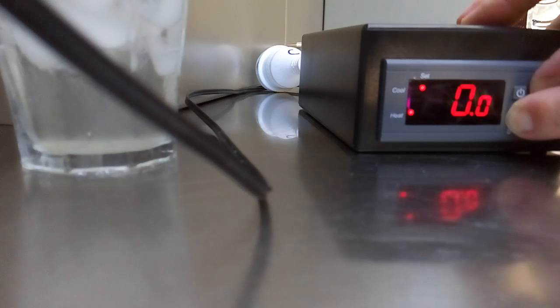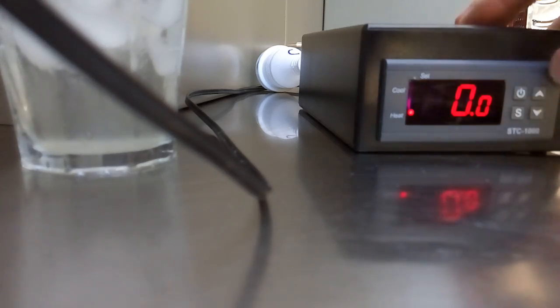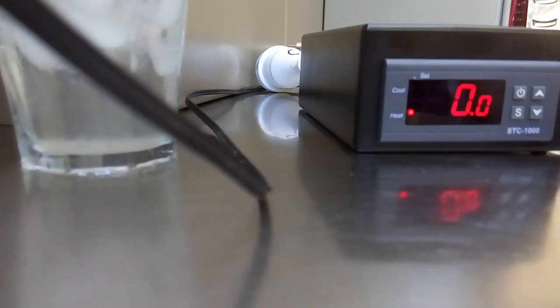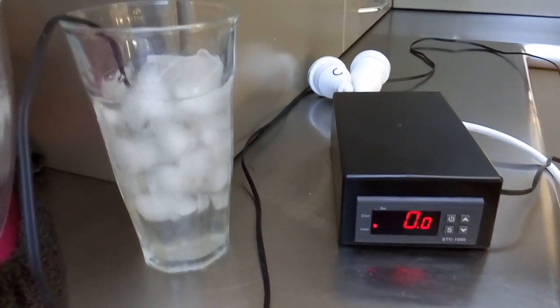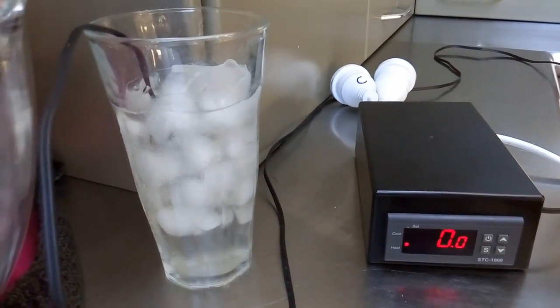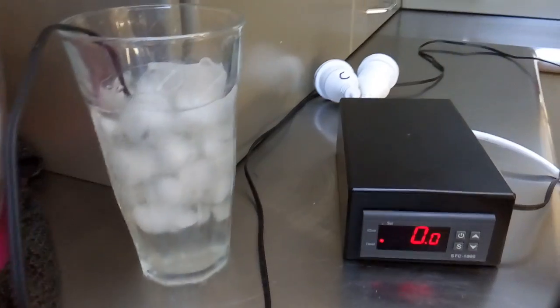Adjust it by how much you're out. So in this case I'm out by 0.1, hit the set button, and you can see now it's showing 0.0. So now I know that my STC is bang on.